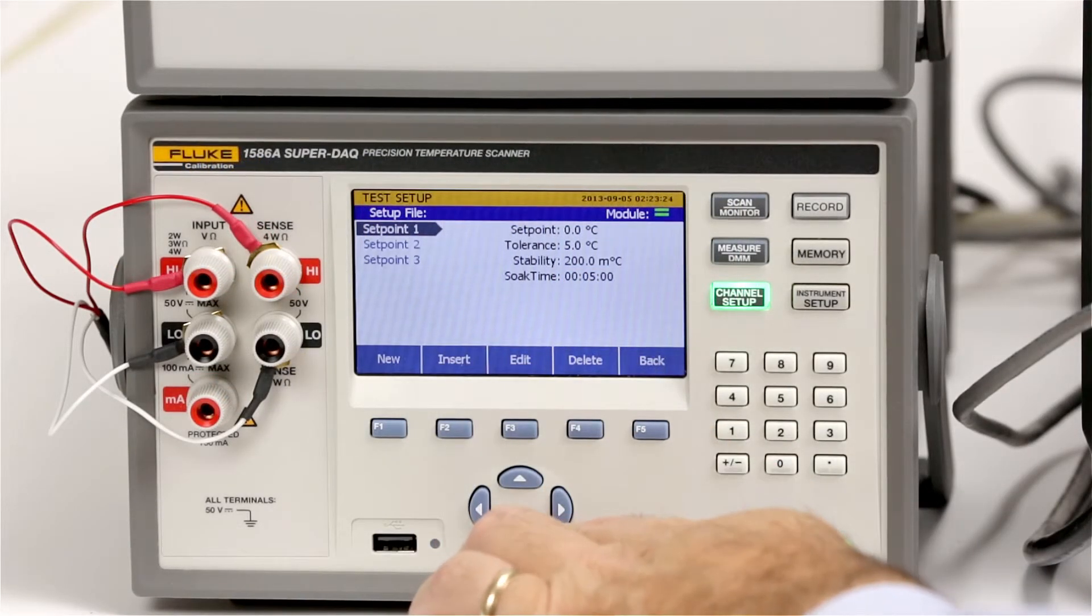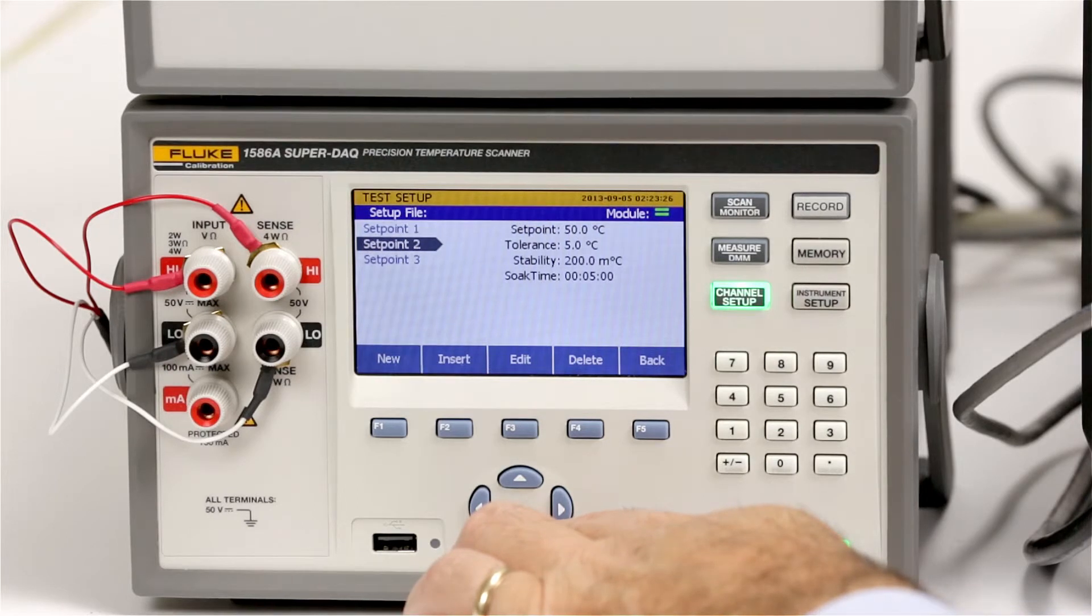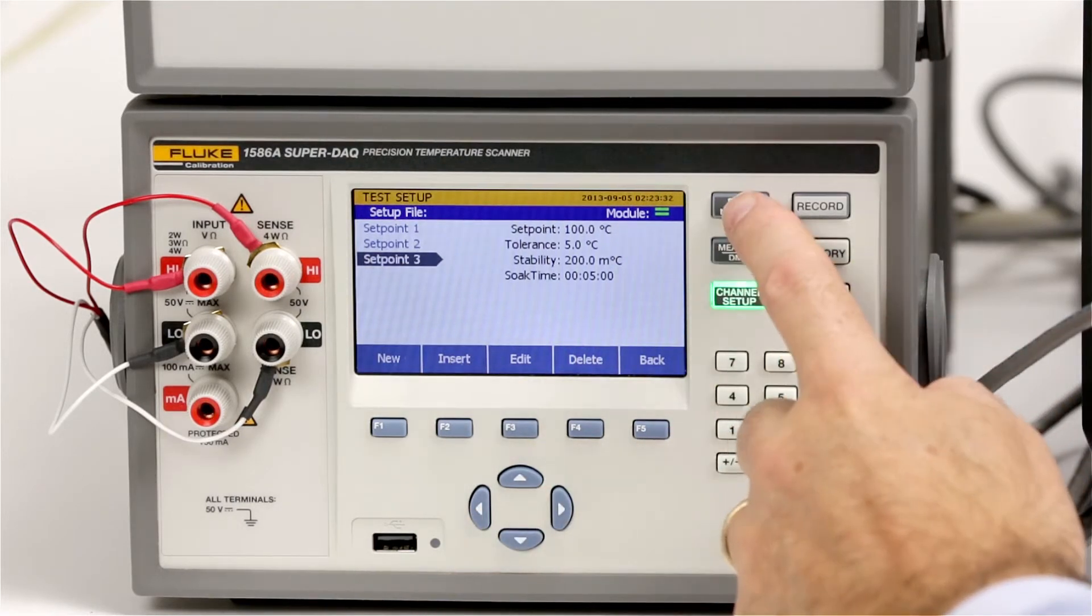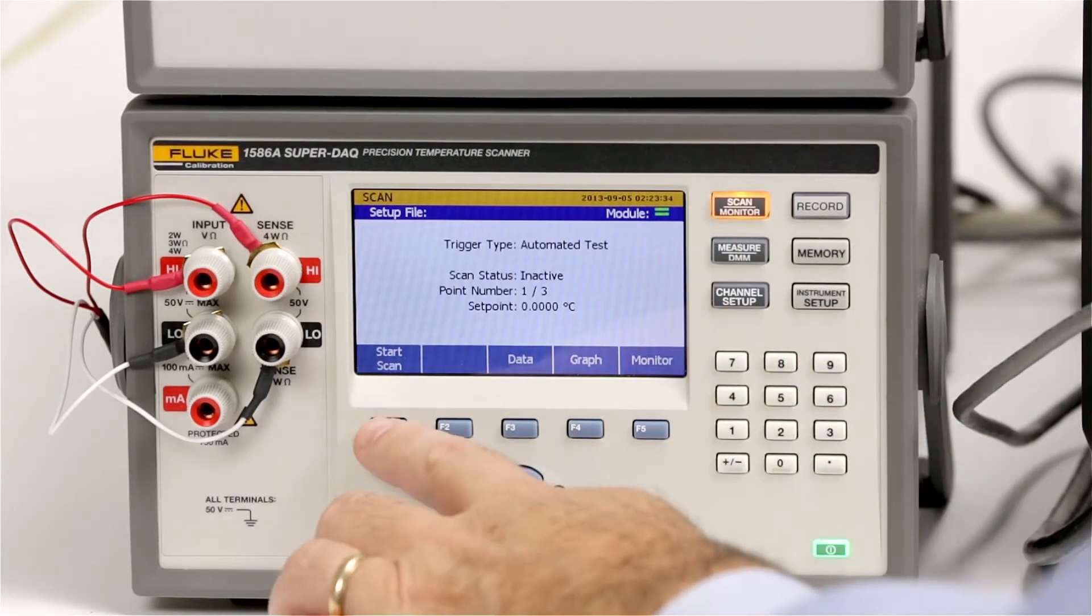Then we'll enter set points at 50 degrees C and 100 degrees C using the same tolerance, stability and soak time values. Press the scan monitor key and select start scan.